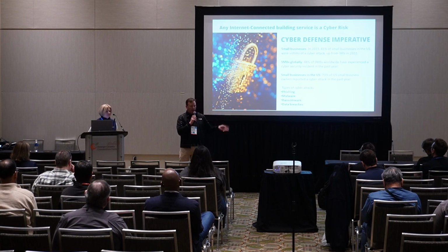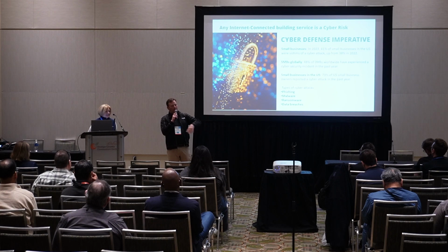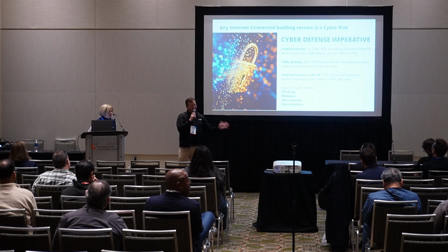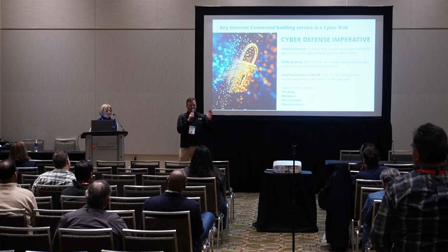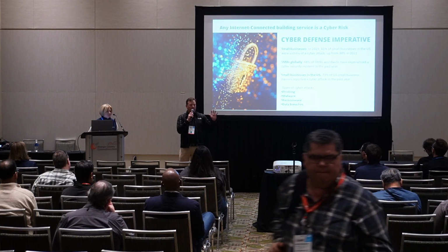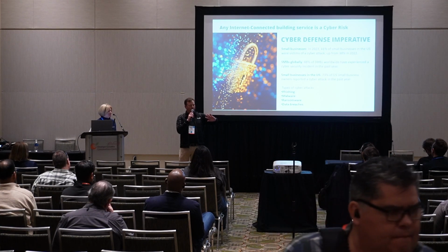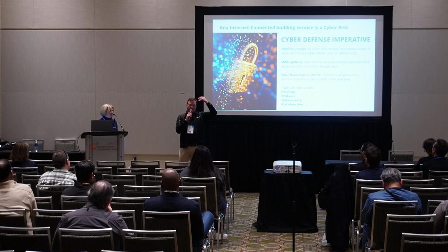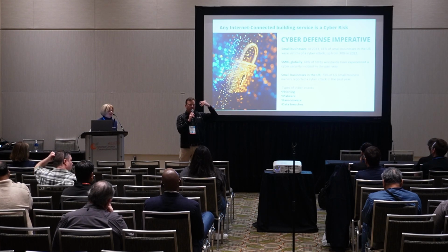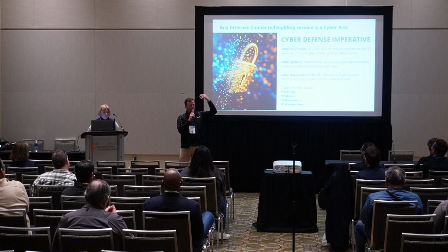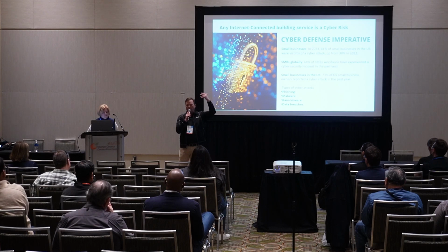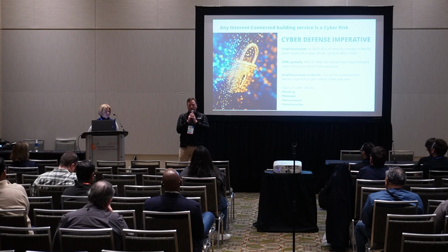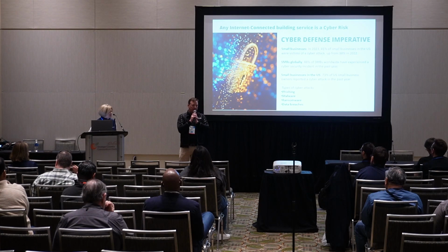Now, right now, BACnet IP is not secure, but they are coming out with BACnet SC, BACnet Secure Connect. A lot of talk about it at the conference. That's going to give us an encryption layer. It's also going to give us certificates. Certificate handling. And certificates, what those do is verify that that device is set up and working on the network the way it's supposed to in a cyber secure manner. And so that's going to help us even more on that layer.